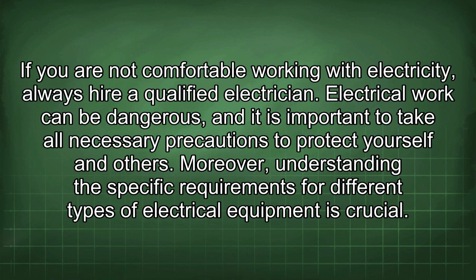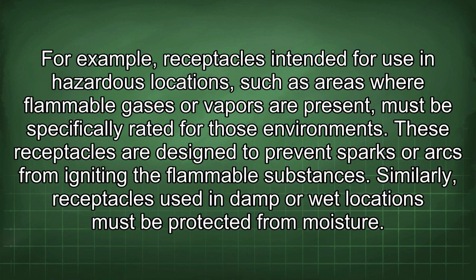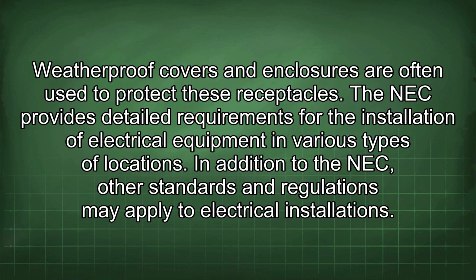Moreover, understanding the specific requirements for different types of electrical equipment is crucial. For example, receptacles intended for use in hazardous locations, such as areas where flammable gases or vapors are present, must be specifically rated for those environments. These receptacles are designed to prevent sparks or arcs from igniting the flammable substances. Similarly, receptacles used in damp or wet locations must be protected from moisture. Weatherproof covers and enclosures are often used to protect these receptacles.